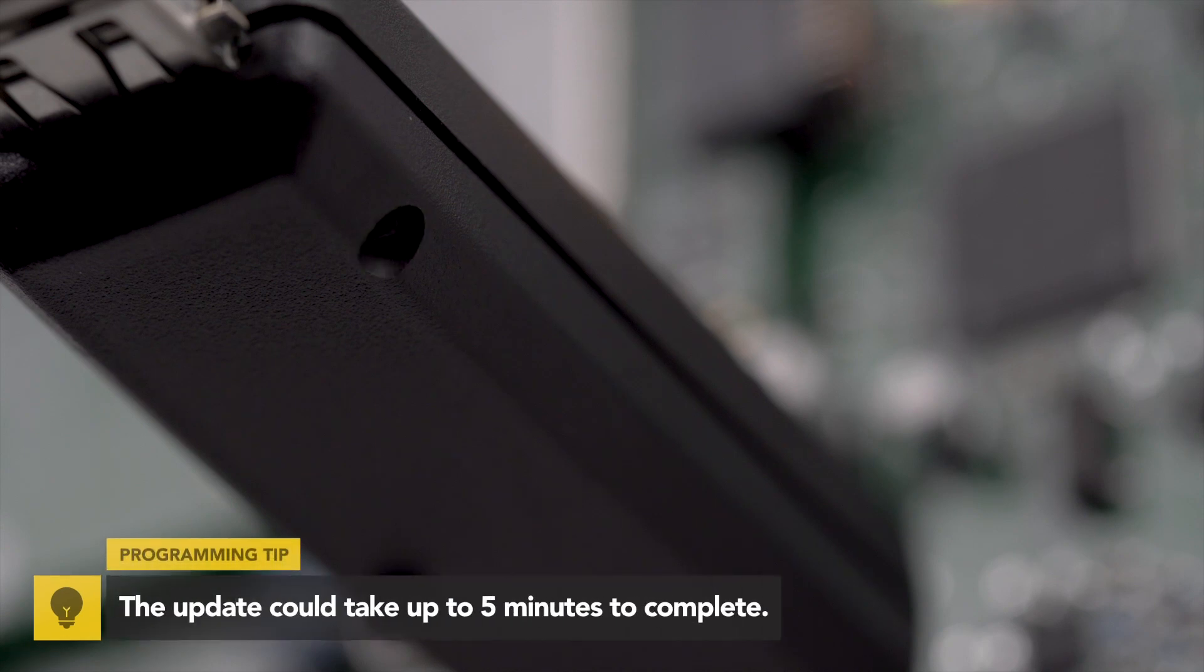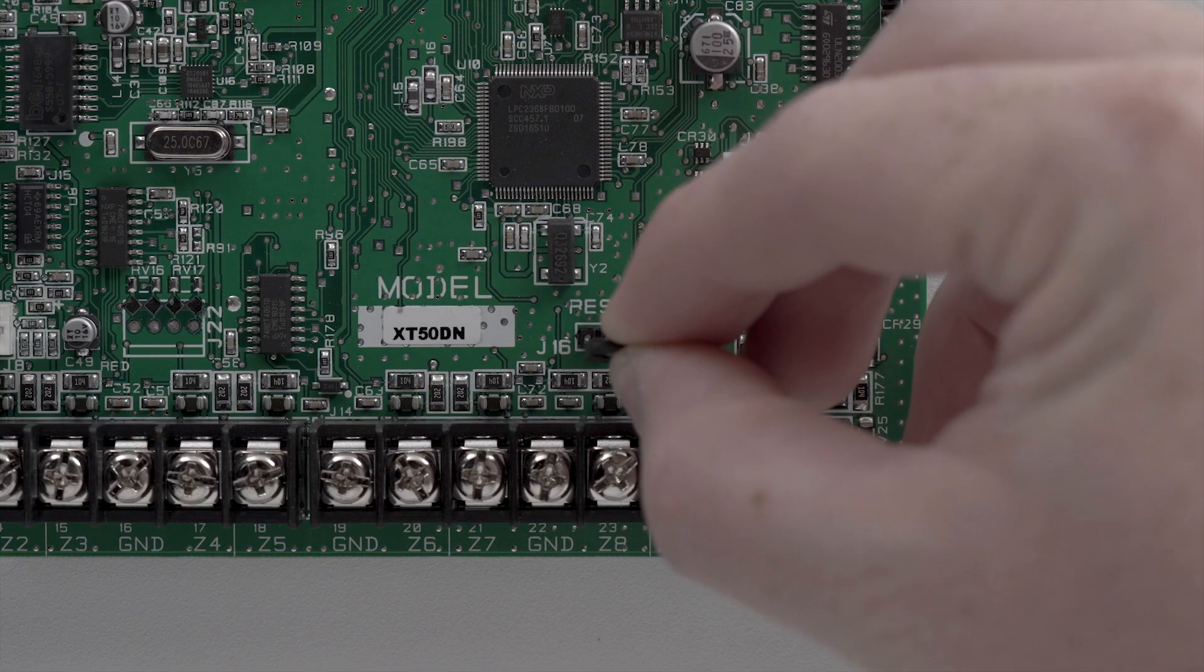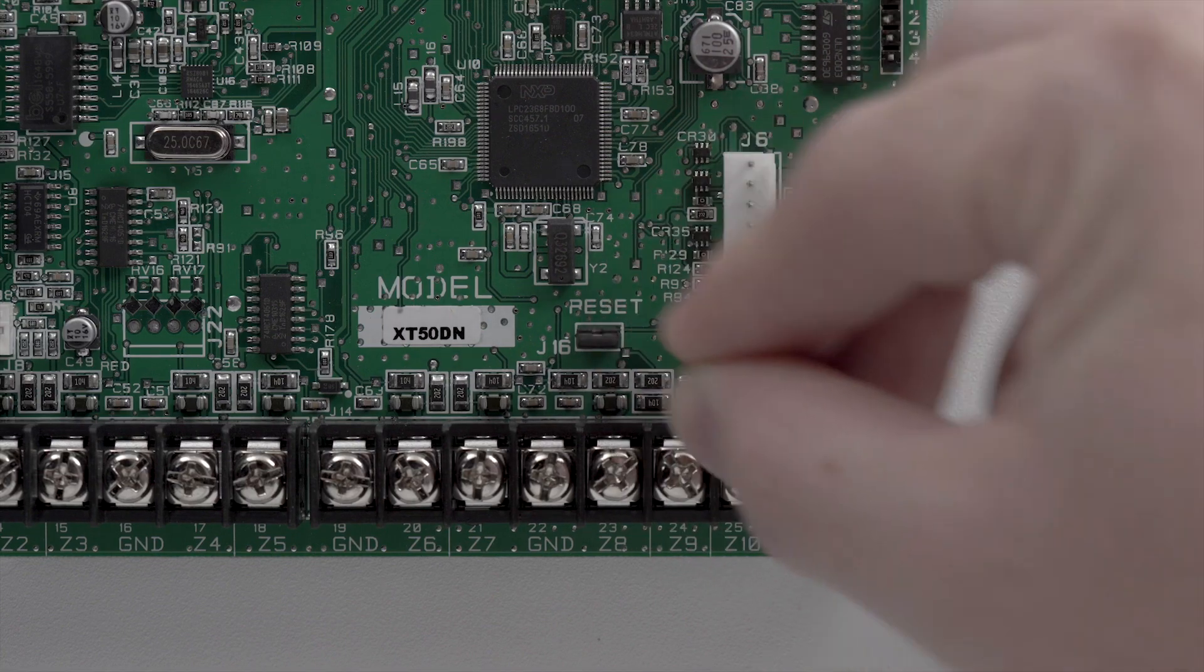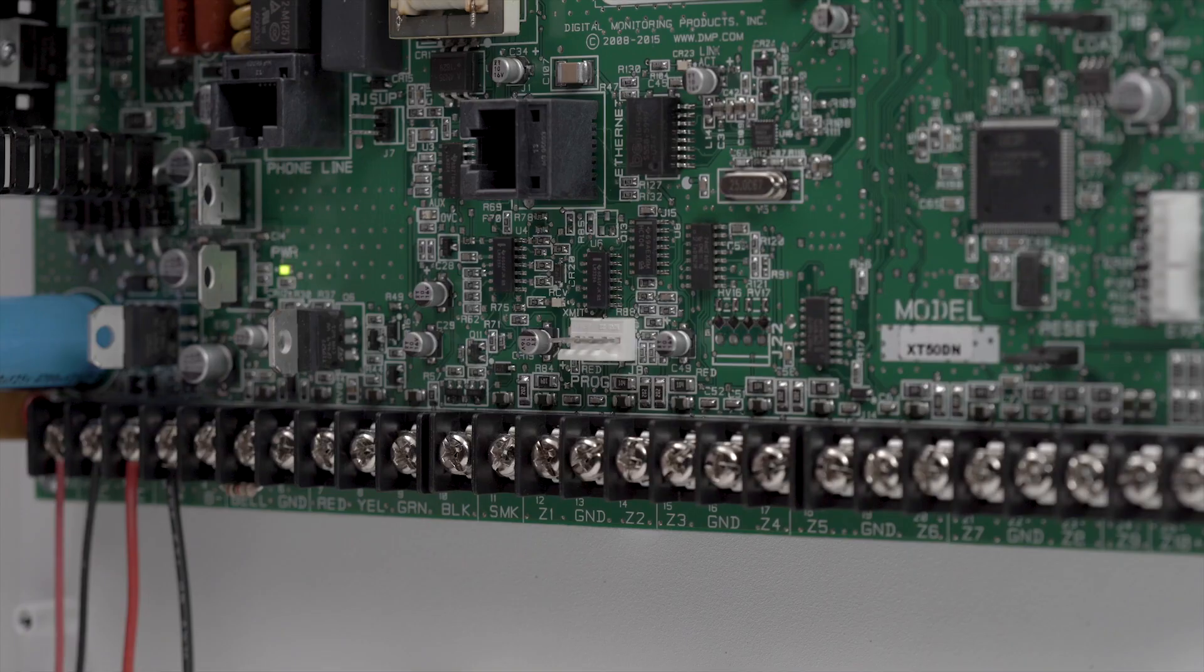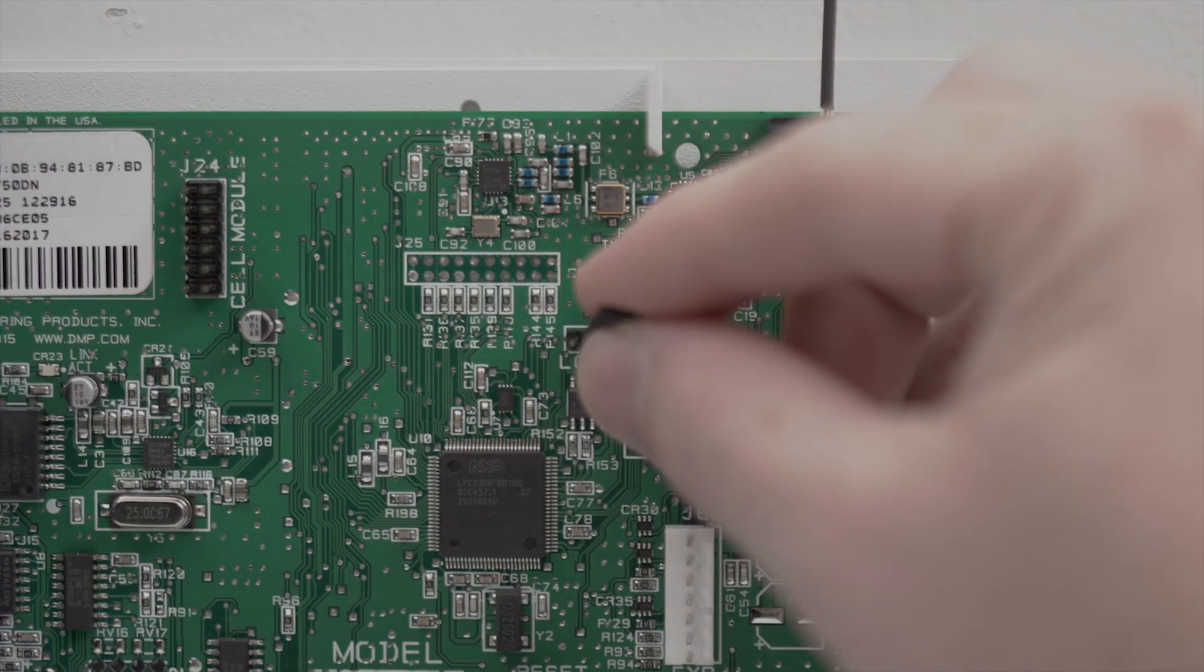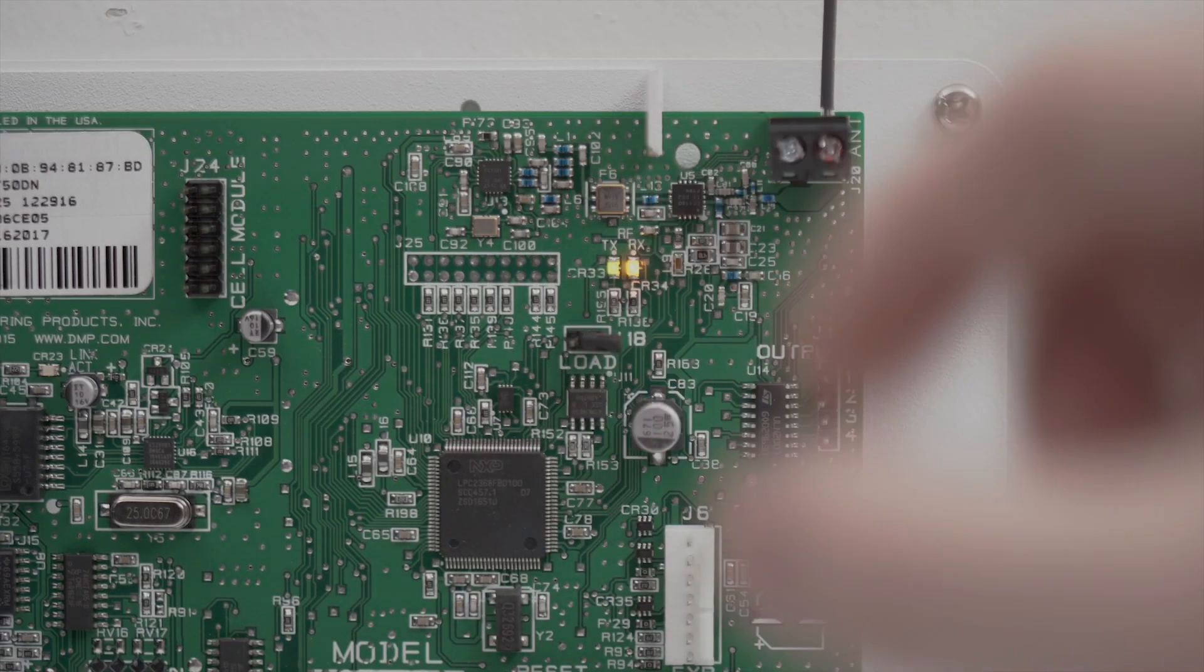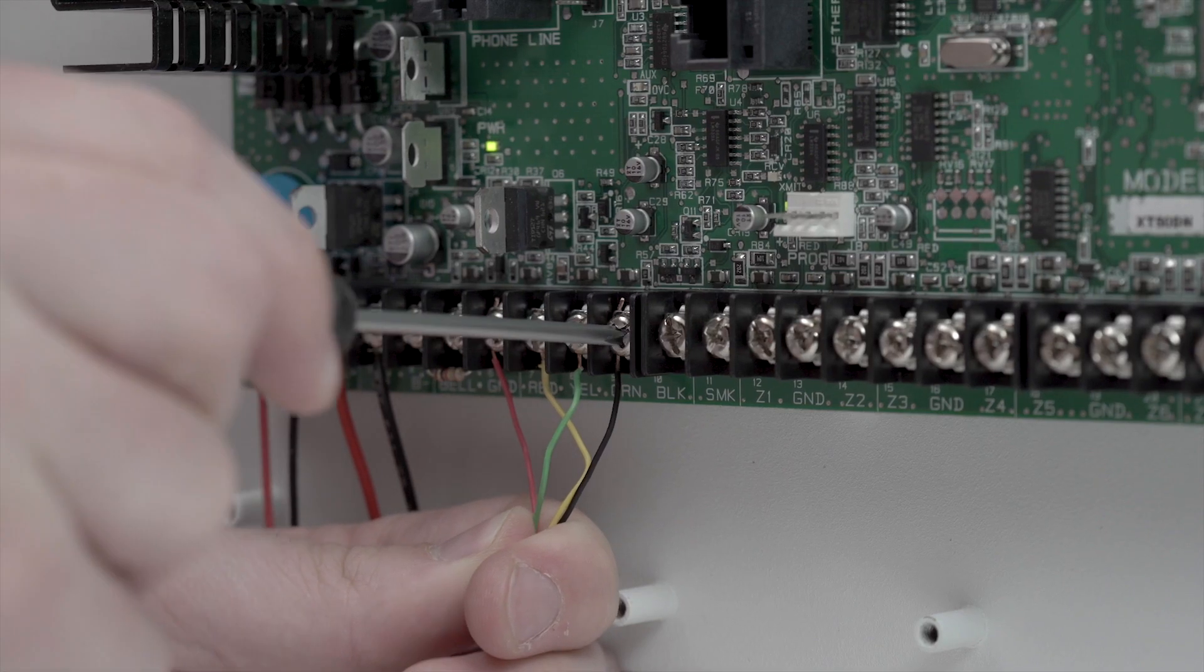When the update is finished, the Model 401 LED will display steady green. Place a jumper across the reset header and remove the Model 401 from the programming header. Then remove the jumper from the load header and reconnect the wires to the keypad bus terminals.